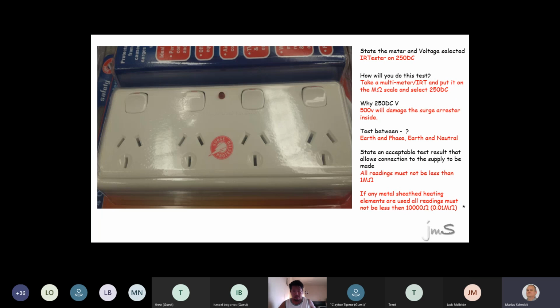If you take a computer and you want to test it, earth to phase, earth to neutral, you must probably use 250 volts, extra low volt, for the insulation resistance on the actual computer itself. Yep, because it's earth to phase, earth to neutral. But it will warn you. If that warning is not there, we always use 500. So the insulation resistance test on the computer is to make sure that no metal parts will become live.